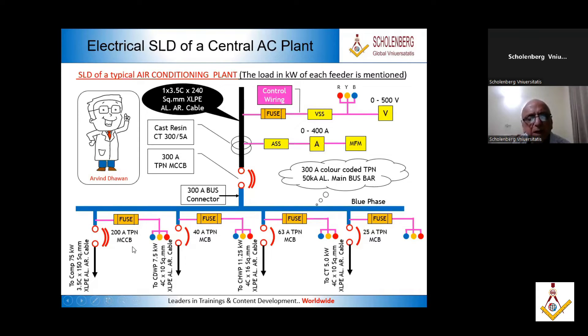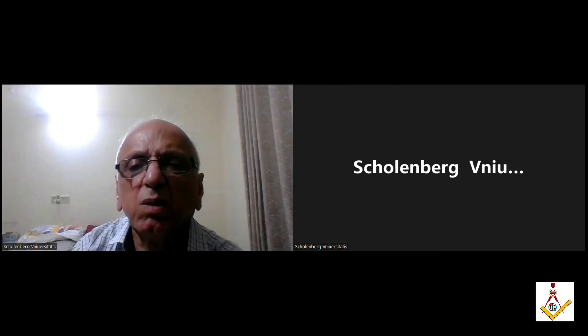This is a 200 ampere TPN MCB, a 40 ampere TPN MCB, a 63 ampere TPN MCB, and a 25 ampere TPN MCB. So this is a complete SLD which mentions the kilowatt load, the cable capacity, the type of insulation, and then the bus bars. Everything is shown here and wiring is done according to this. So that was the question asking about the SLD.